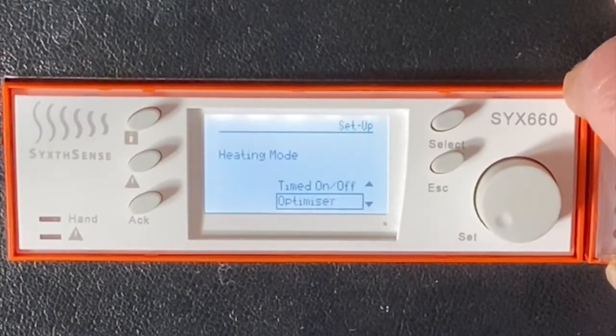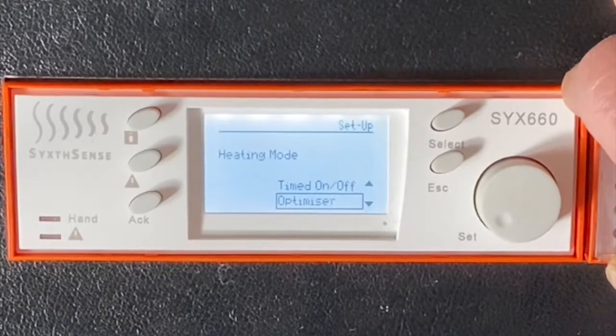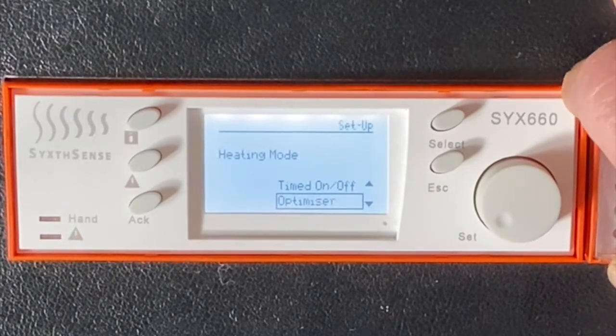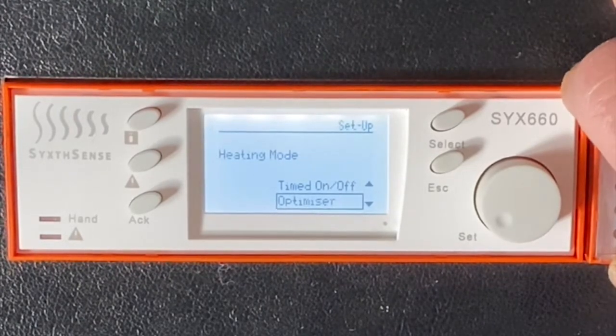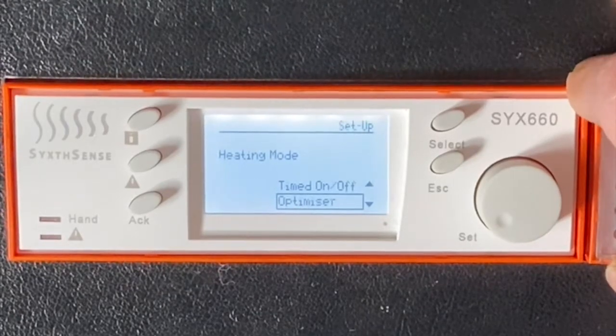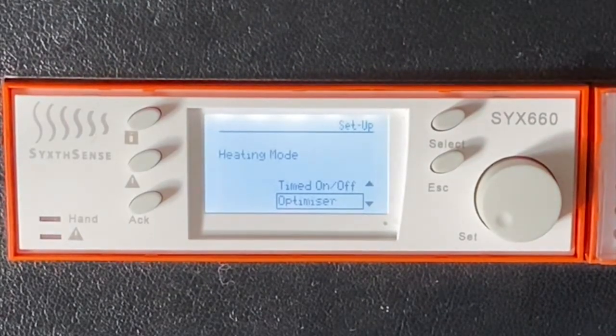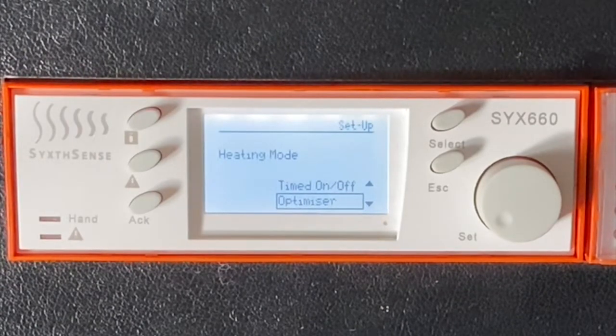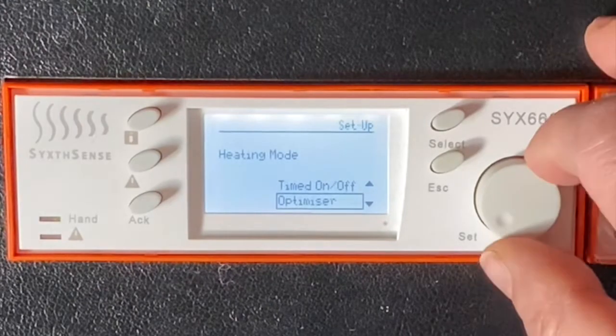Optimizer only, this is where we use the pump output to start and stop plant based around an optimized start signal. It will turn on for optimum start, remain on for the rest of the day, and follow the optimum off if it's enabled. There is no control functionality with that application. It purely is an optimum start capability.